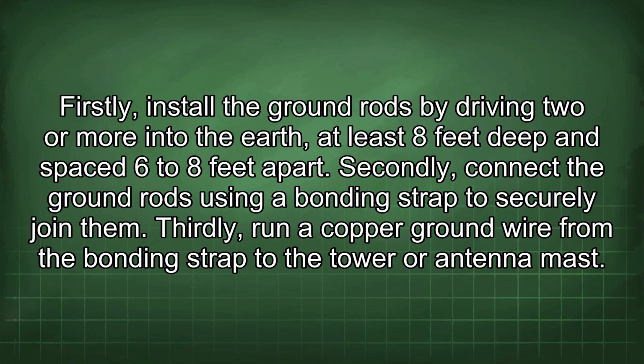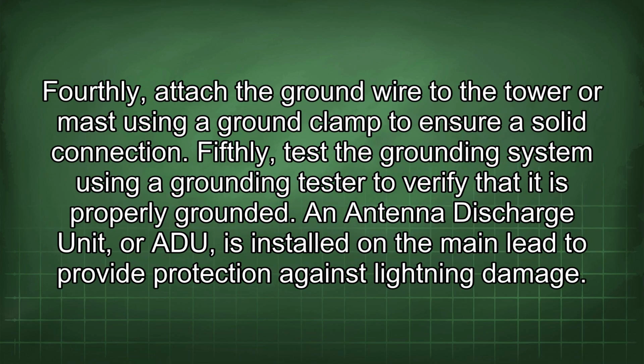Thirdly, run a copper ground wire from the bonding strap to the tower or antenna mast. Fourthly, attach the ground wire to the tower or mast using a ground clamp to ensure a solid connection. Fifthly, test the grounding system using a grounding tester to verify that it is properly grounded. An antenna discharge unit, or ADU, is installed on the main lead to provide protection against lightning damage.